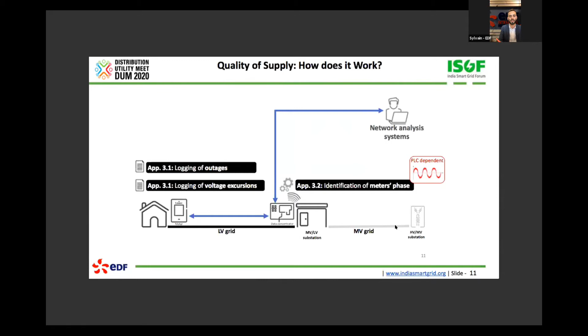Network mapping: we have this phase identification I was explaining, to know which phase the meter is connected to, but we also have the identification of the link between the meter and the distribution transformers. We'll see it on the slide here. This is what we call the beauty of PLC: the telecommunication link is more or less the same as the electrical link, so it's possible to recompile this and to re-establish the electrical grid topology.